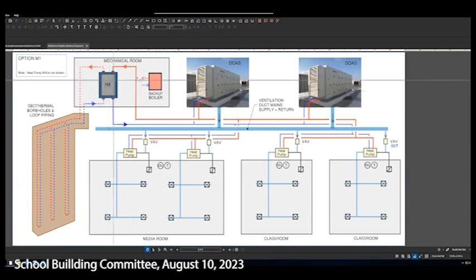And so that water on the inside building loop is circulated around. It's going to the DOAS units, which are a water-cooled heat pump kind of unit, versus the air-cooled heat pump type that we use in the VRF option. A typical classroom, instead of being served by a refrigerant-based fan cooling unit, is served by a heat pump that gets that water piping connected to it. That's its heat sink. It's going to absorb heat from the water, or reject heat to the water, depending on whether it's heating or cooling, and then it's delivering that air to the classrooms. Again, you see the VAV box, which is delivering ventilation air from the outdoor air system to the space. That very much operates the same way. So the real difference here is, for the geothermal option, the heat sink is the ground. For the VRF option, the heat sink is the air.